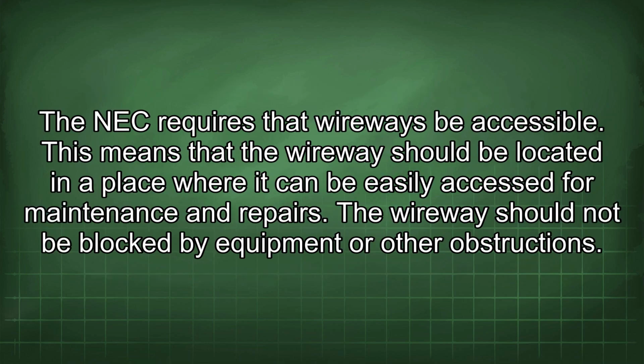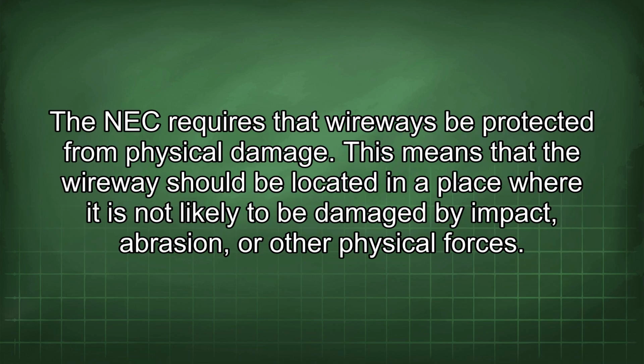The NEC requires that wireways be accessible. This means that the wireway should be located in a place where it can be easily accessed for maintenance and repairs. The wireway should not be blocked by equipment or other obstructions. The NEC requires that wireways be protected from physical damage. This means that the wireway should be located in a place where it is not likely to be damaged by impact, abrasion, or other physical forces.